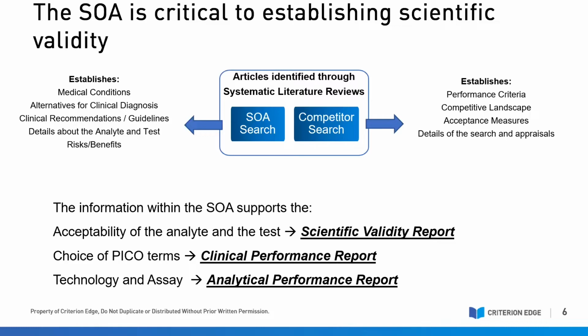And now finally, you will need to define your competitive landscape. Competitors are not the same thing as alternatives, so keep that in mind. This section is where you will establish the safety and performance measures as well as your acceptance criteria using the data that you have extracted from many articles that you've retrieved through your competitor searches. The goal is to compare your IVD to your closest competitor IVDs, and then you will use the PER to show that your IVD performs as intended and meets these pre-established acceptance criteria. So be prepared to document each of these searches in detail, and you should be expecting that you need to present your results very clearly.